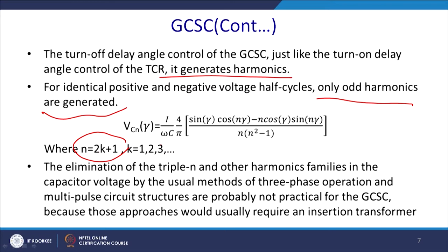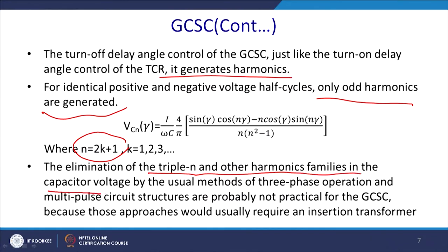We require to eliminate those harmonics. We had eliminated harmonics by different delta connections in the case of TCR, and the same principle can be applied here. However, elimination of triple-n and other harmonic families in the capacitor voltage by three-phase operation and multi-pulse circuit structures is probably not practical in the case of GCSC, because those approaches would usually require insertion of a transformer.